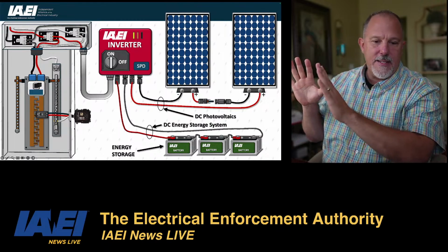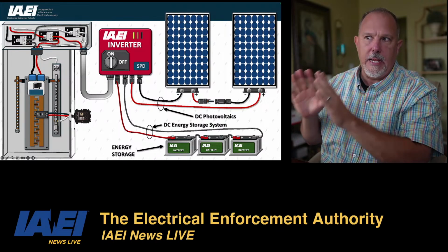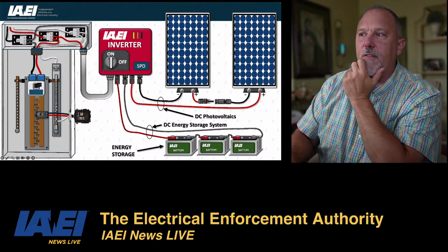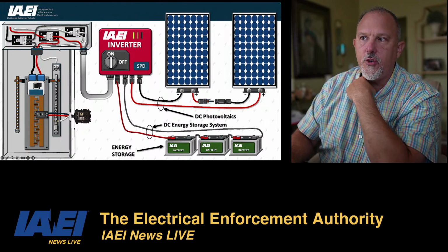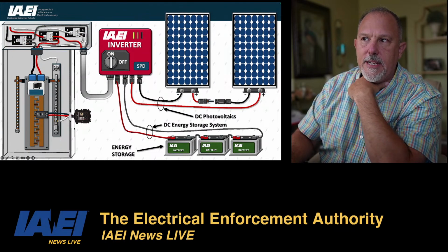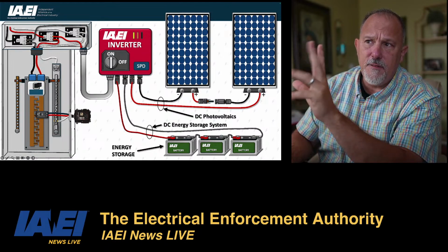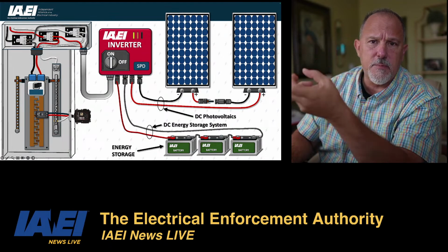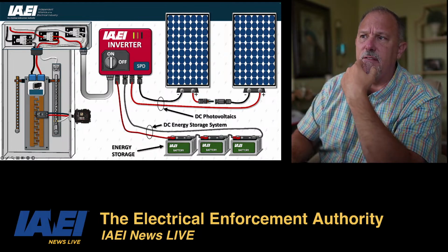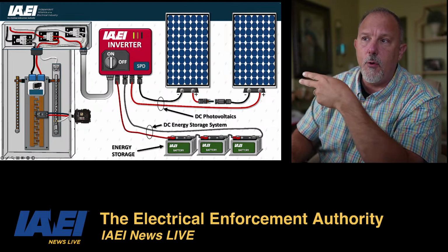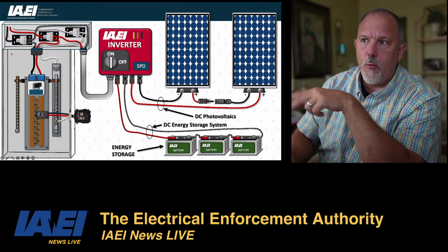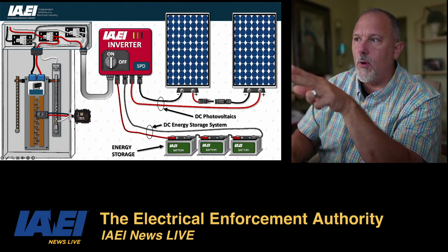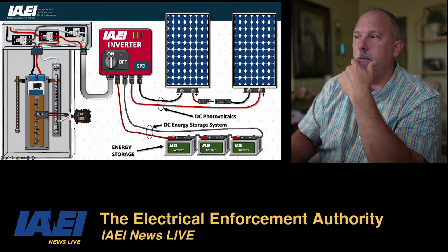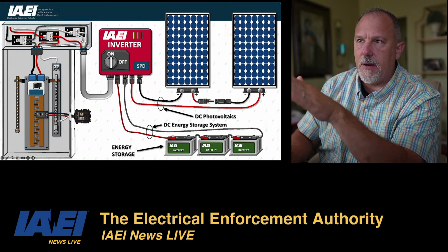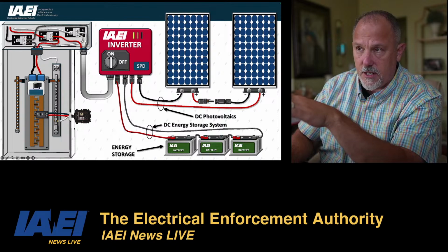So don't take any of these diagrams as gospel. Please point out any issues. And let me know if there's a different way you connect into service equipment. I just showed power distribution blocks. I didn't show, there's Polaris configurations. There's split lugs and bolts and all that good stuff. I'm showing one conductor coming in and two going out. One set of service conductors going to the panel board and one set of service conductors going to this inverter. All right, so we talked about the power distribution blocks. We talked about the service conductors. Let's talk about this neutral.